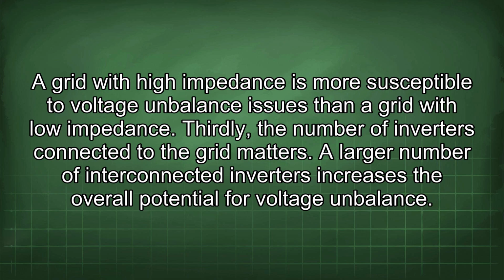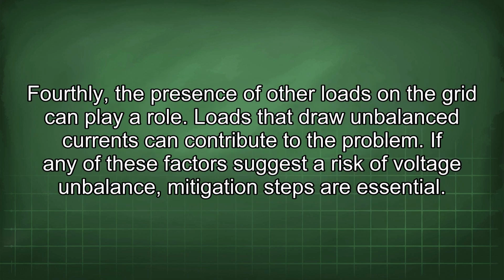Thirdly, the number of inverters connected to the grid matters. A larger number of interconnected inverters increases the overall potential for voltage unbalance. Fourthly, the presence of other loads on the grid can play a role. Loads that draw unbalanced currents can contribute to the problem. If any of these factors suggest a risk of voltage imbalance, mitigation steps are essential.